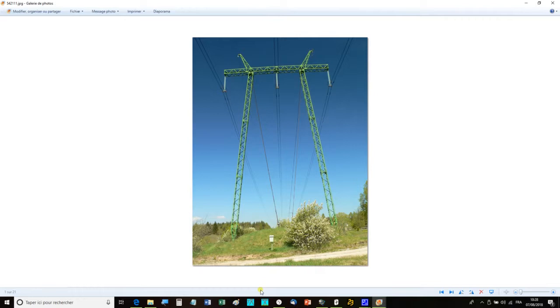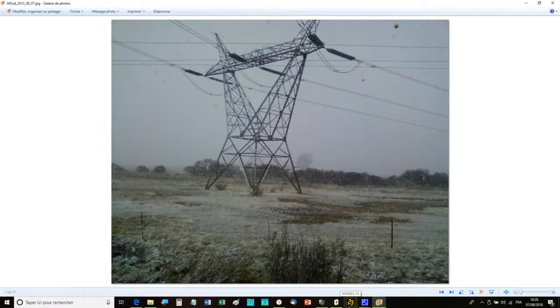Before building an overhead power line, a study must be done to know which supports should be used, where to place them, what tension should be applied to the conductors so that at the lowest possible cost, the line would be strong enough to withstand the worst storm that may occur where it will be built, so that the clearance around the conductors will remain safe at all times.